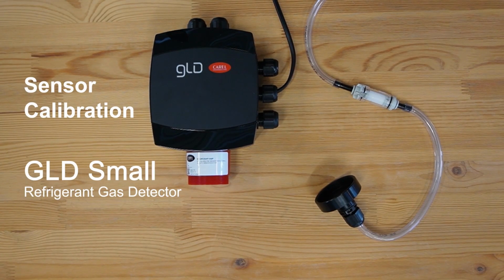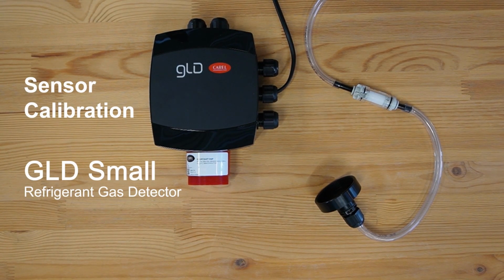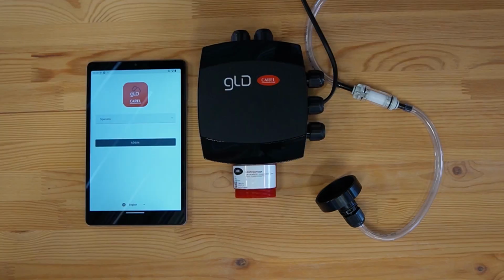Welcome to this step-by-step guide on how to calibrate the sensor on the GLD small refrigerant gas detector. To calibrate the sensor, you will need the service app, which you can download for free for iOS and Android, a calibration kit, and a test gas with a known concentration, typically between 50 to 100% of the measuring range of the sensor. Make sure the sensor is warmed up completely.